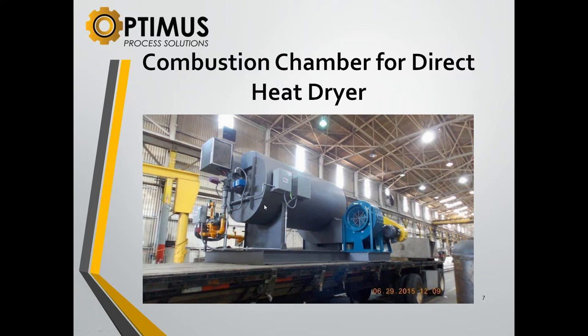And on the other end, we have a process air fan that's bringing the gases in that will cool those combustion gases. So if you're combusting air at, say, 30% excess air, and you're running at 2950 or 3000 degrees, and you want the air coming into the dryer, it would be attached right here, then you can run this fan on a variable frequency drive to bring in whatever air you need to make those hot gases whatever temperature you need coming into the dryer. So that fan is there to control the temperature coming out.